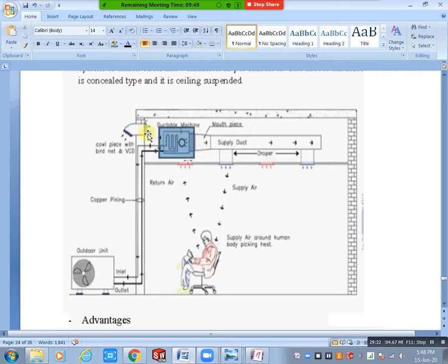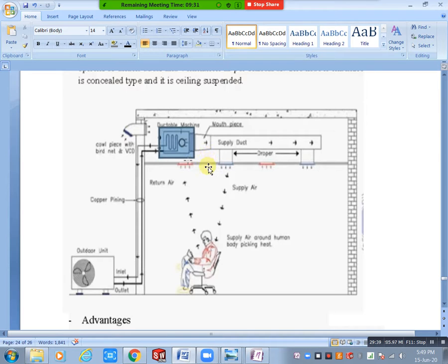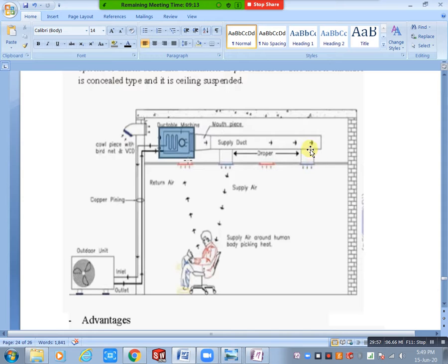There are return air diffusers and supply diffusers. The entire system runs above the false ceiling — so you cannot see it inside the room, keeping the interior clean. Supply air terminals are directly connected to the duct. For return air, we consider free return — no ducts for return. This will be discussed in our next class when we do load calculation.